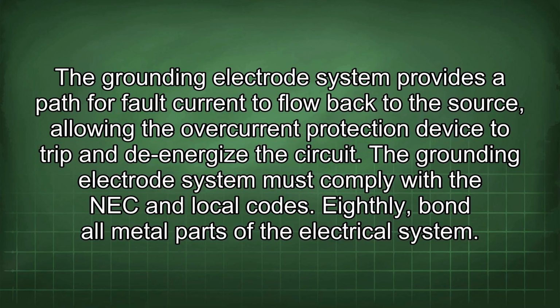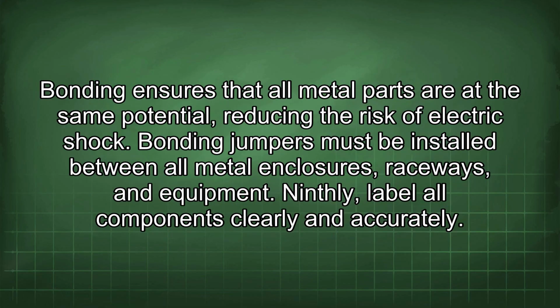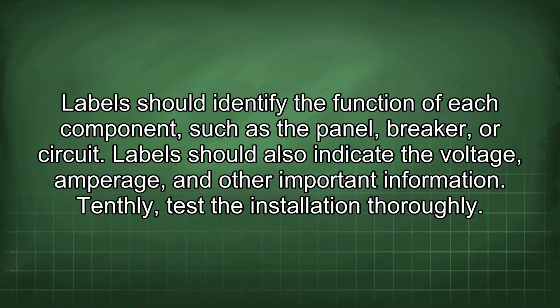Eighthly, bond all metal parts of the electrical system. Bonding ensures that all metal parts are at the same potential, reducing the risk of electric shock. Bonding jumpers must be installed between all metal enclosures, raceways, and equipment. Ninthly, label all components clearly and accurately. Labels should identify the function of each component, such as the panel, breaker, or circuit. Labels should also indicate the voltage, amperage, and other important information.